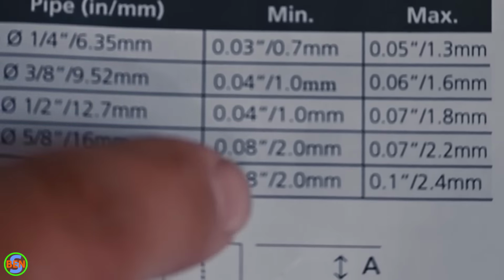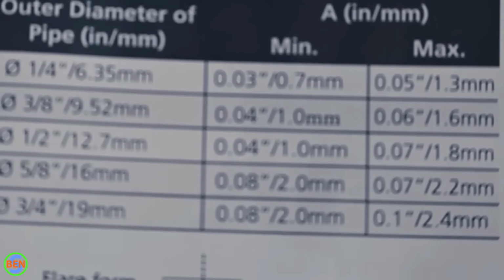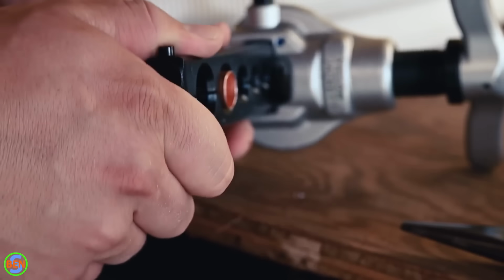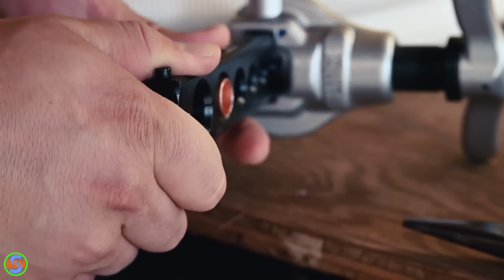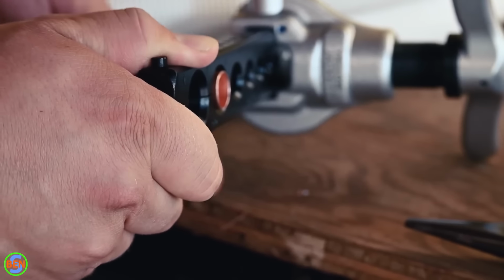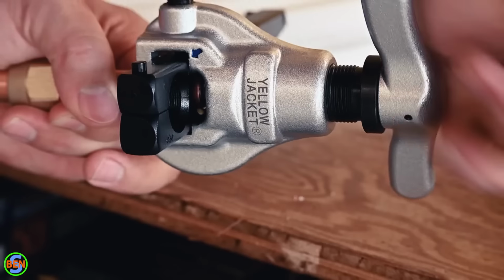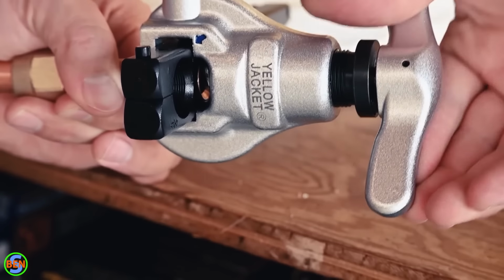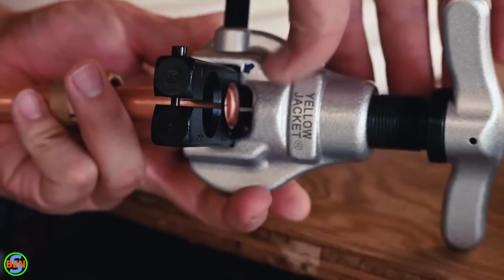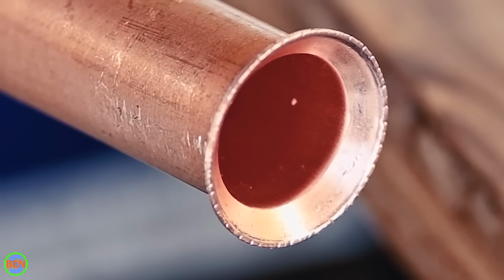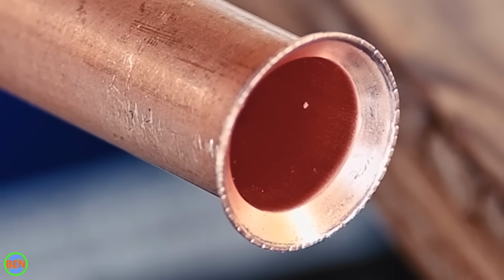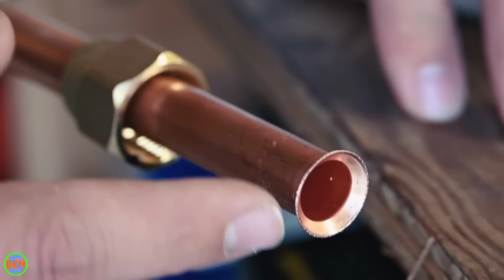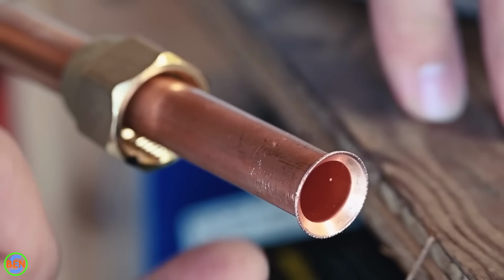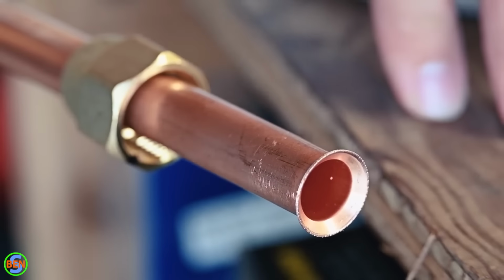Now we'll take our flaring tool, and according to this chart, they want it to be anywhere between 2 millimeter and 2.2 millimeters, so right at around 1/16 of an inch. Pretty much just eyeball that height. Let's go ahead and make our flare. Made contact right about there. Now we'll back it off. We can see that the face right inside of this flare is really nice and smooth, and that's the spot that matters. That's where the seal is made between the copper pipe and the brass fitting that it connects to.